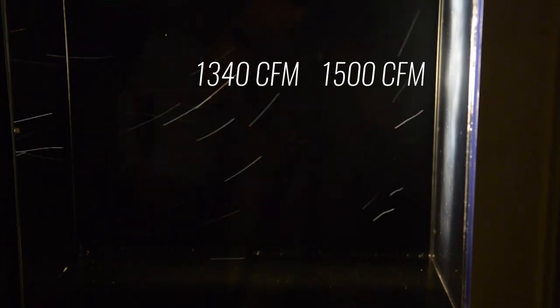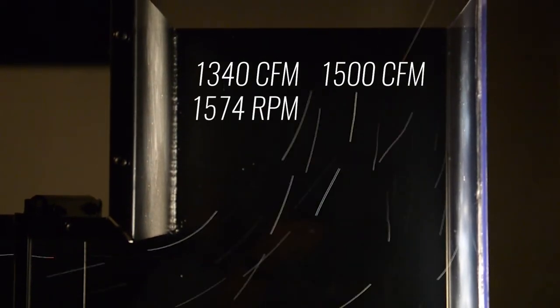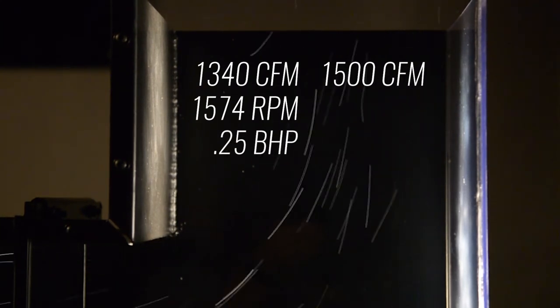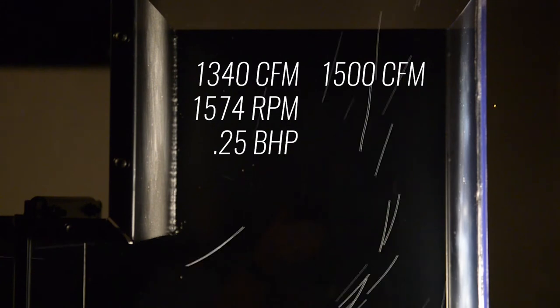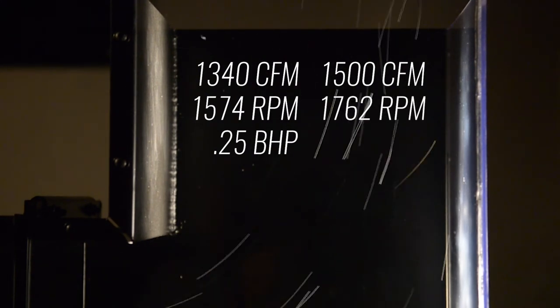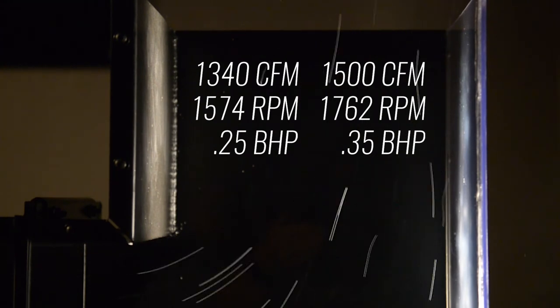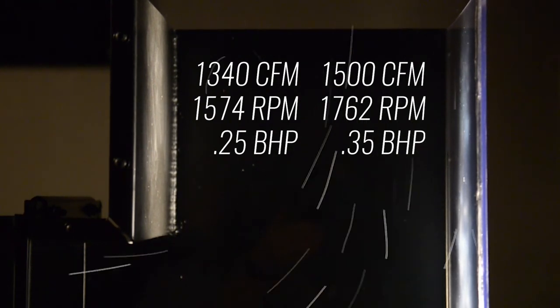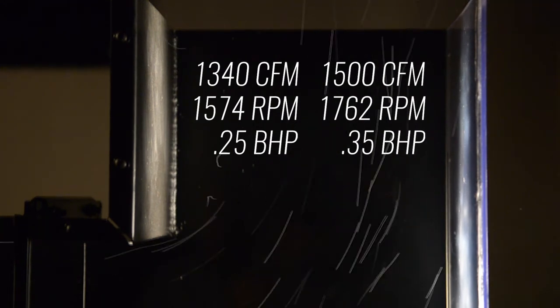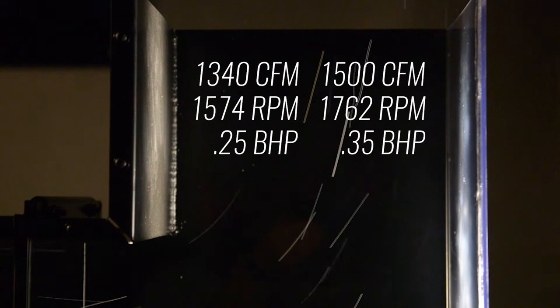Let's take a minute to evaluate the ramifications. If we encountered this in the field and needed 1500 CFM and are only getting 1340 CFM, we would need to speed the fan up to get the required airflow. Our demo fan is running 1574 RPM and consuming 0.25 brake horsepower. Using the fan laws, we calculate that the fan would need to run 1762 RPM with a new brake horsepower of 0.35 to get the required airflow. Unfortunately, in this case, the motor on our demo fan is a quarter horse motor and would need to be replaced with a larger motor to get the required performance. You can see the problems that can arise when the system pressure is not fully accounted for.